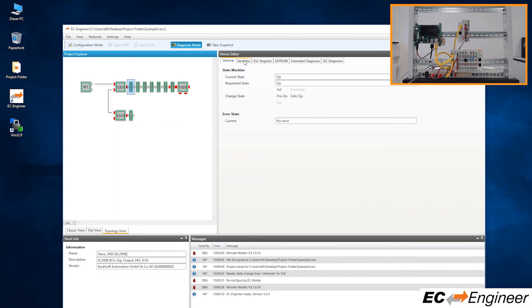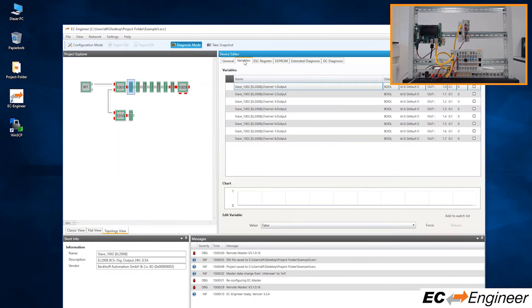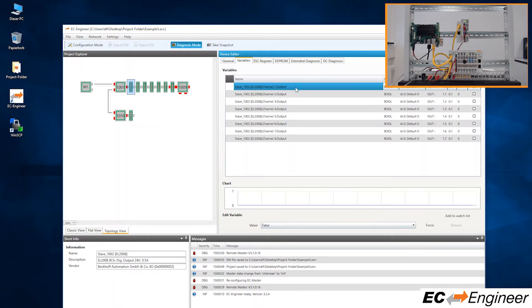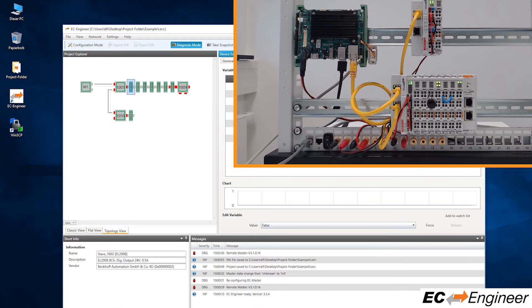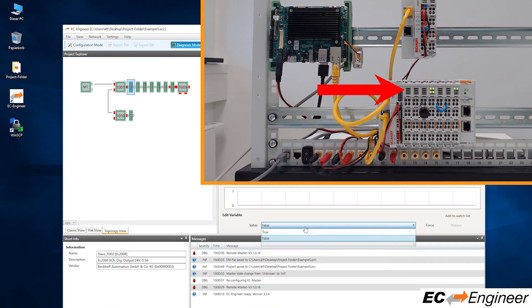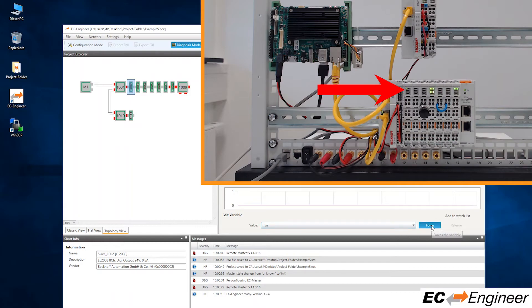Select the first slice module, which is an output module, and we will force the first output variable and observe the change on the physical device by the LED coming on and off, highlighted in red.